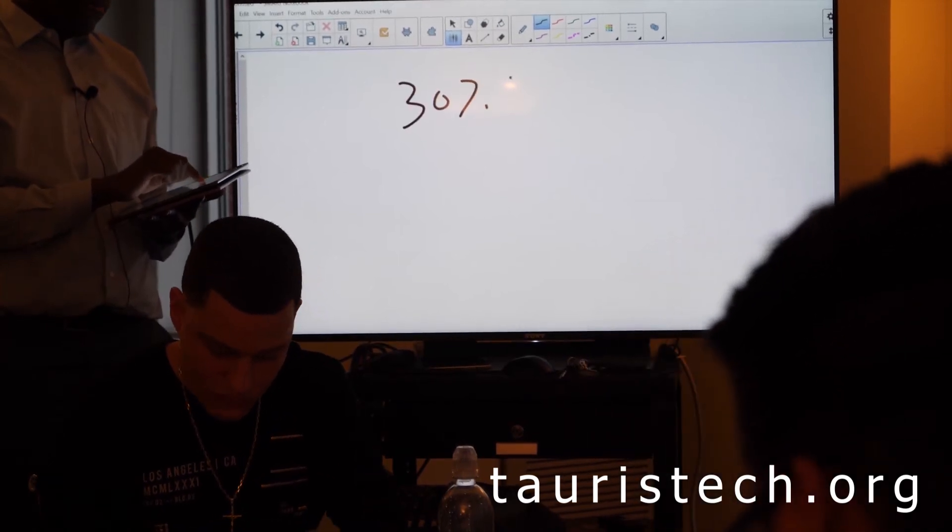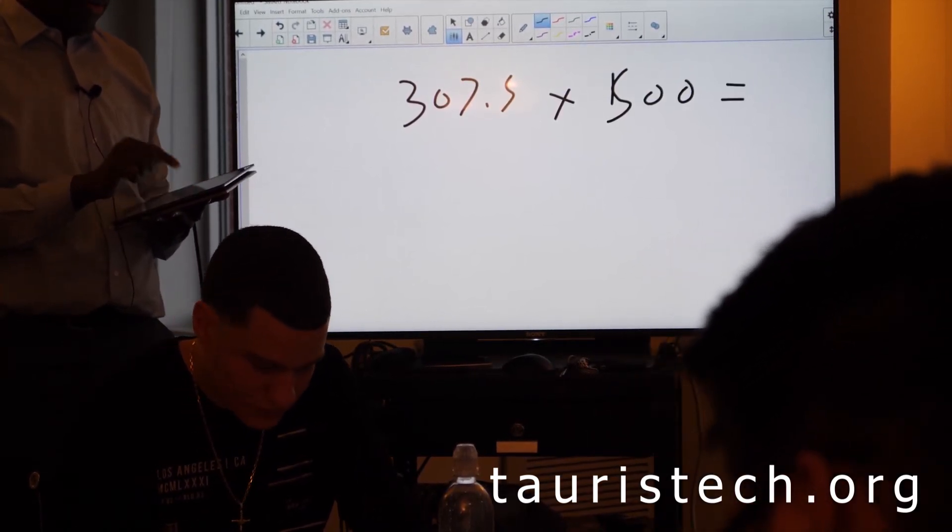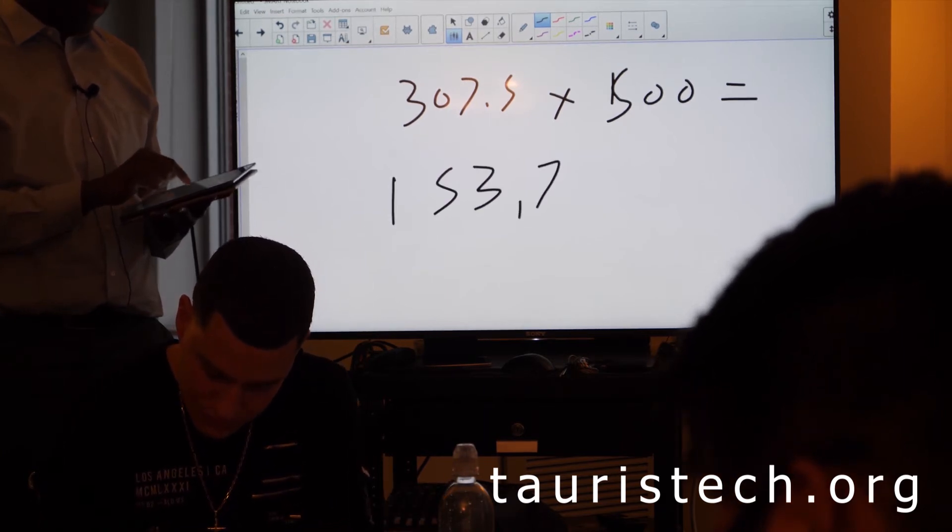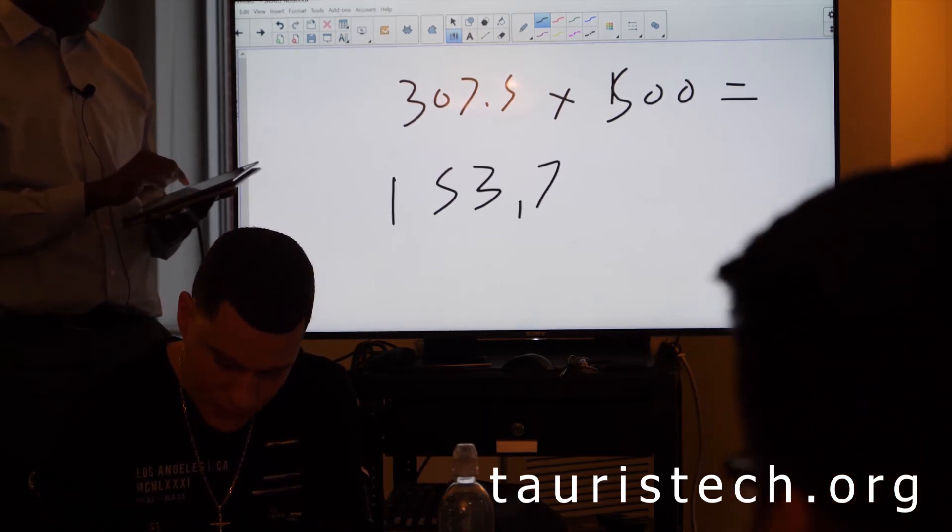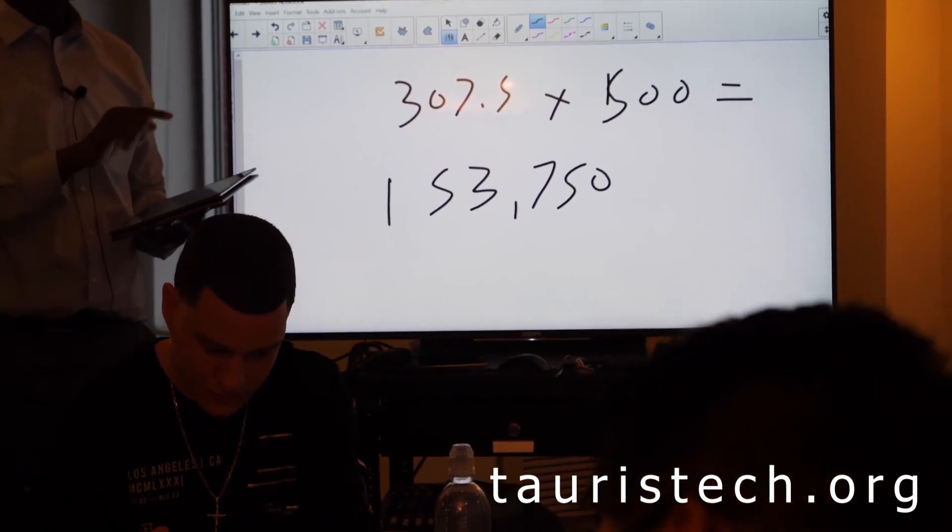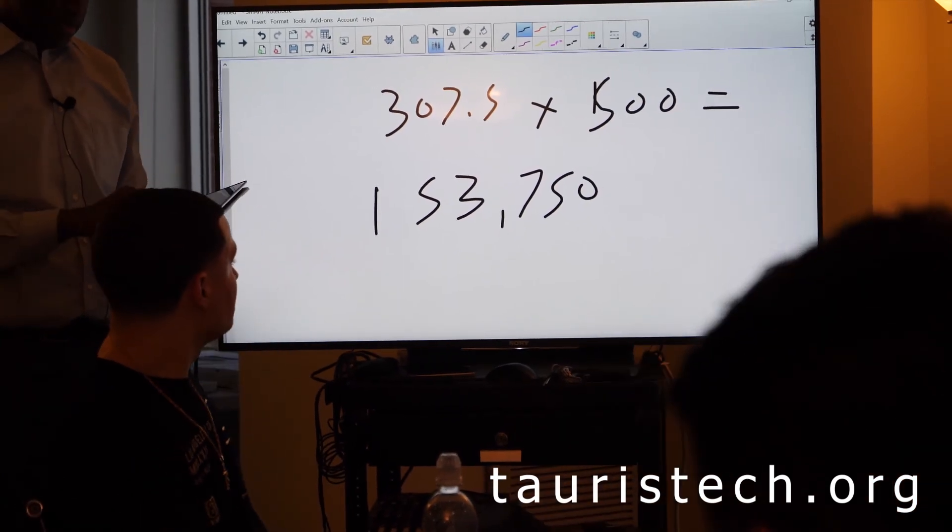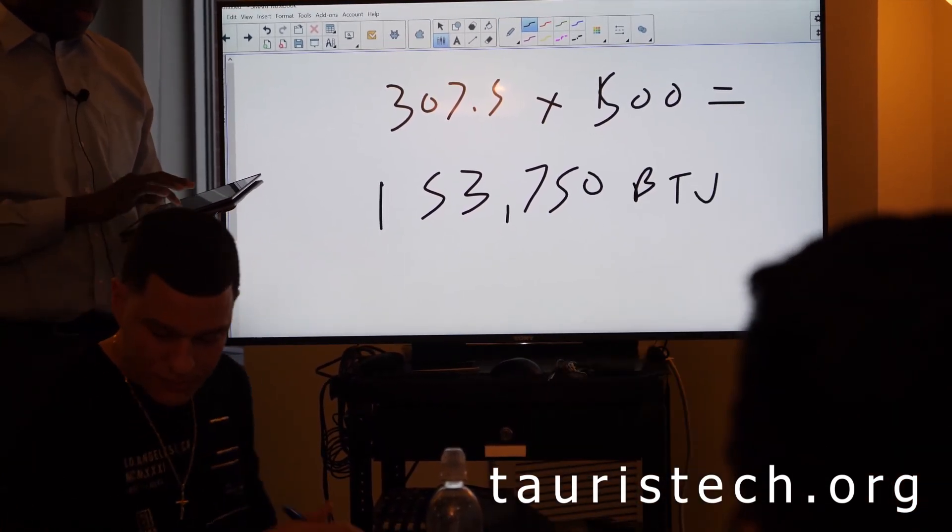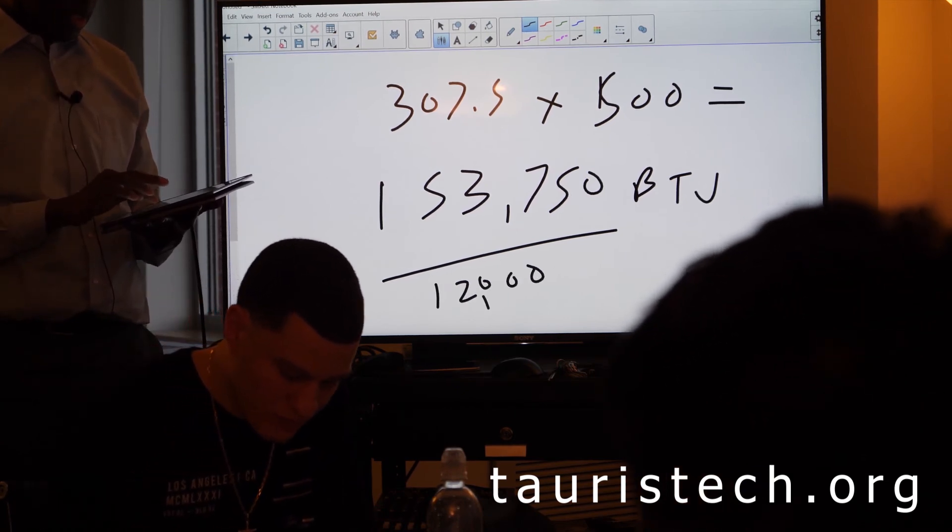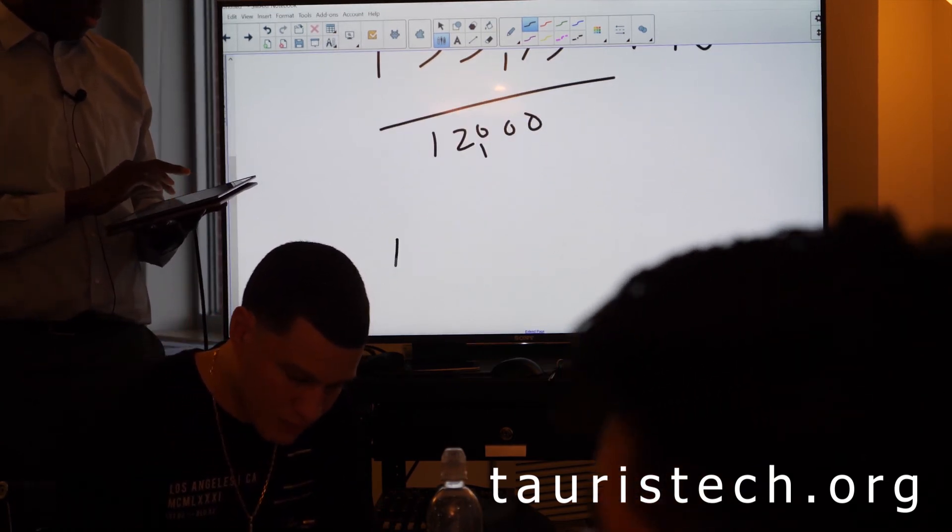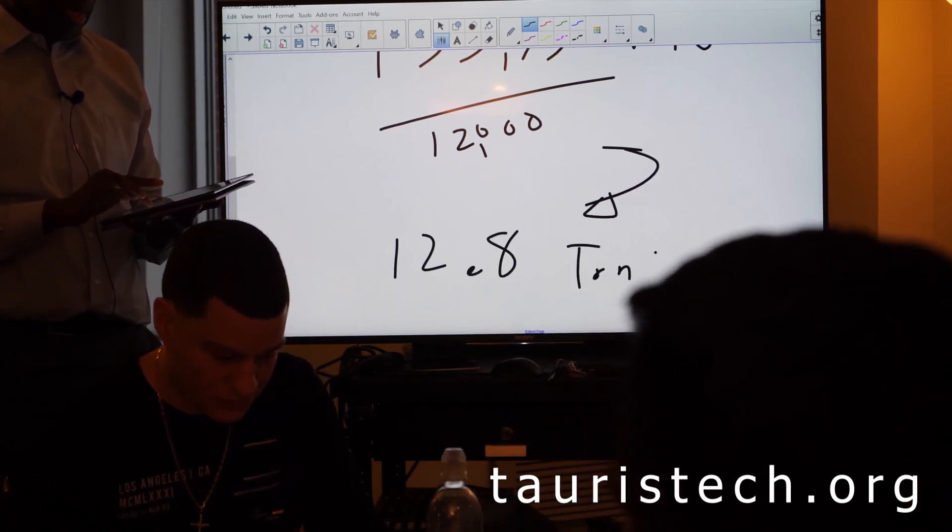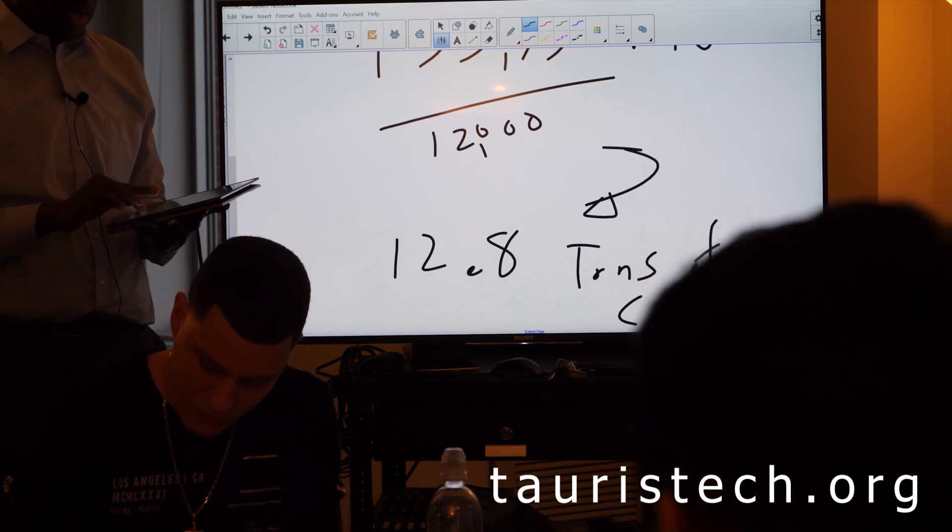307.5 times 500 equals 153,750 total BTU. What do we do with that? Divide by 12,000 to get tons of cooling.